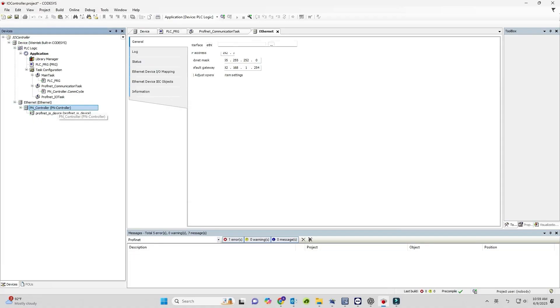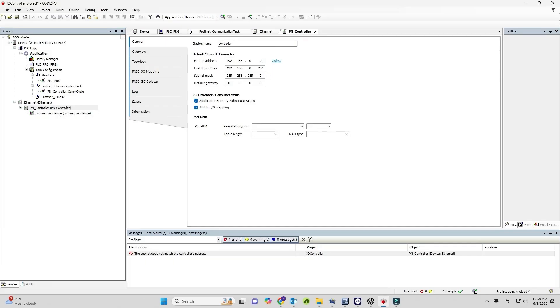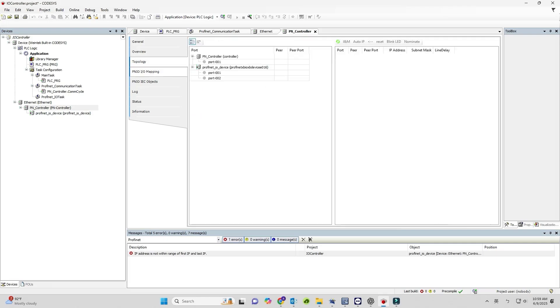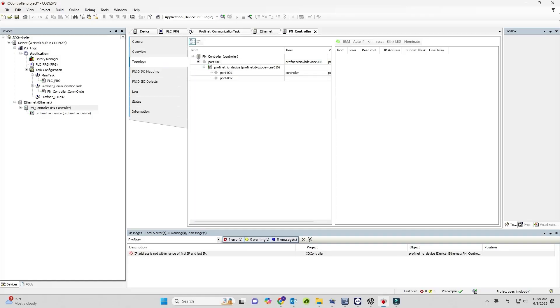Next, open PN controller, General, and set the IP address range for PROFINET I/O devices. Devices outside this range won't be able to communicate. In PN controller, Topology, choose the communication port.